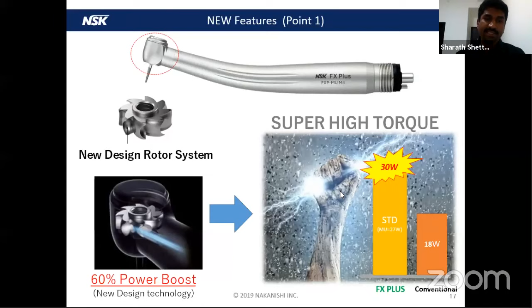Now, what is this pressure regulating valve? There is a specialized valve inside this handpiece which prevents damage to the cartridge from excessive air pressure. That means even if the air pressure is beyond the set limit, this pressure regulating valve protects the handpiece from this excessive air pressure. So you don't need to worry that air pressure is high, or of course, if it's low, obviously you will not get the cutting efficiency. But if it's high, there is a possibility of the cartridge, that is the inner rotor, getting damaged. For that, this pressure regulating valve plays an important role.